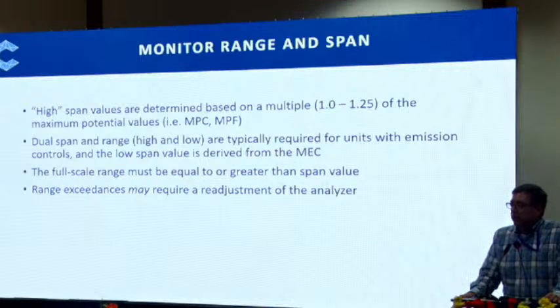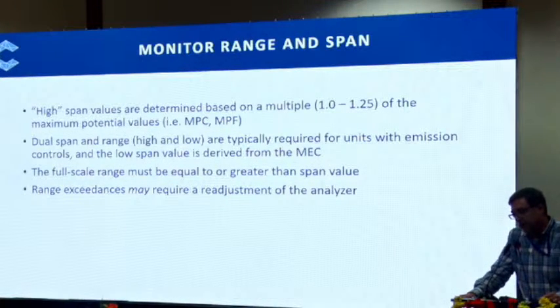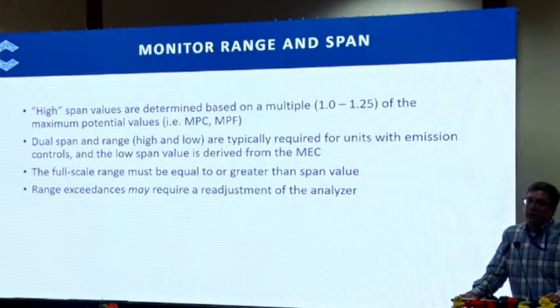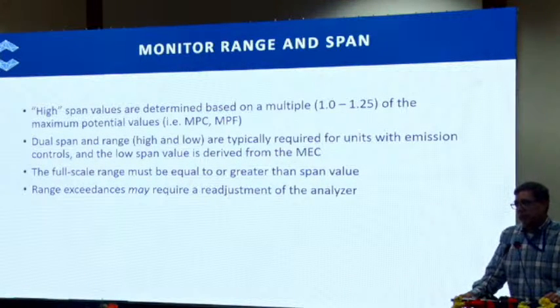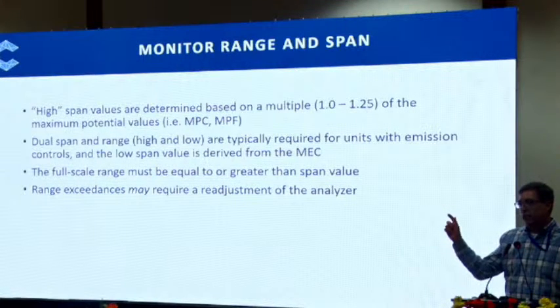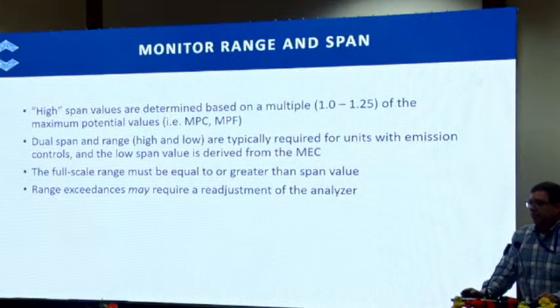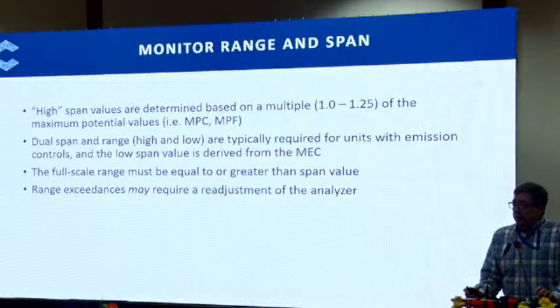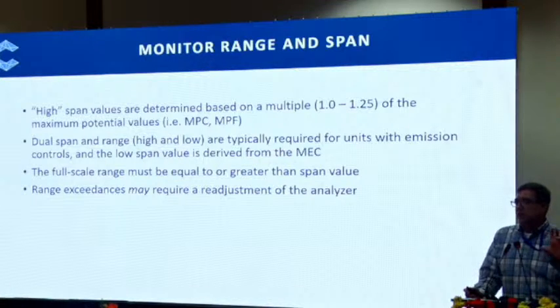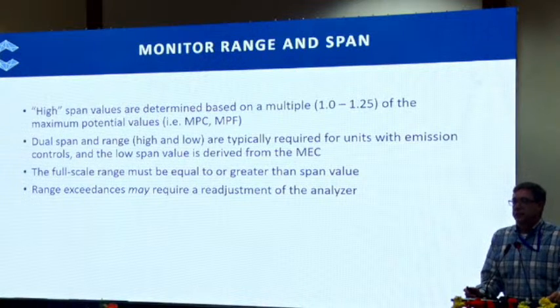The full-scale range must be equal to or greater than the span value. Typically, in the United States, and I would think most instrument providers would tell you this, you want to be between 20% and 80% of the electronic range of the instrument for your span, so you stay out of the low and high end where there could be the potential for noise. Range exceedances may require a readjustment of the analyzer. So if you have a system change, or you install the instrument with good intentions, ideally this should be the maximum potential concentration. However, you may find in normal operation, or even in an upset condition, that you're exceeding that. You can go back, make adjustments and adjust the range. In fact, you are required to evaluate that on a periodic basis.